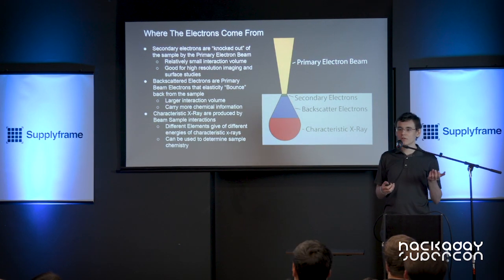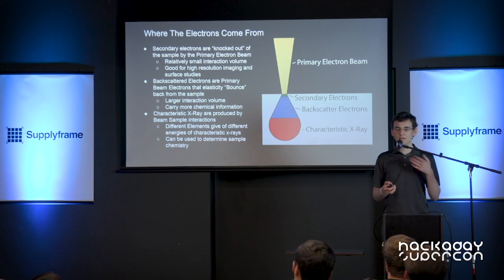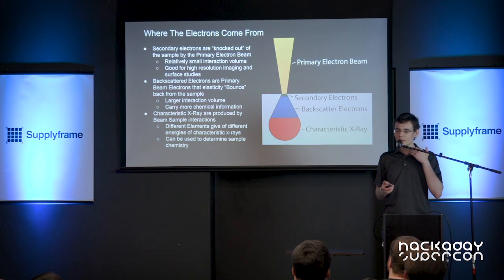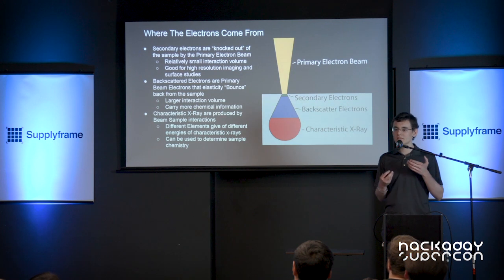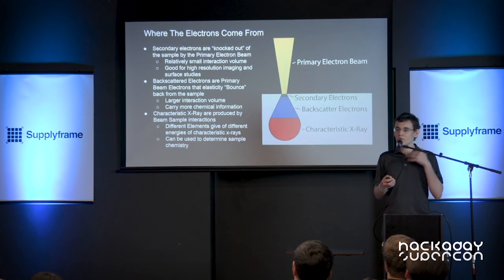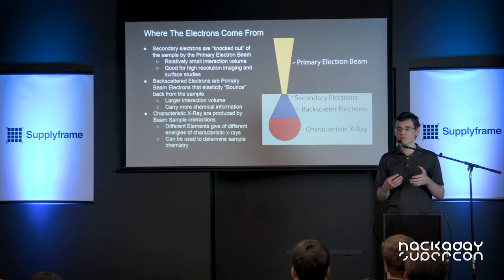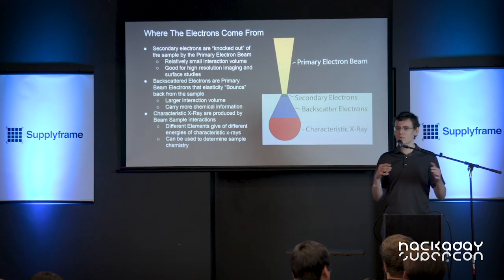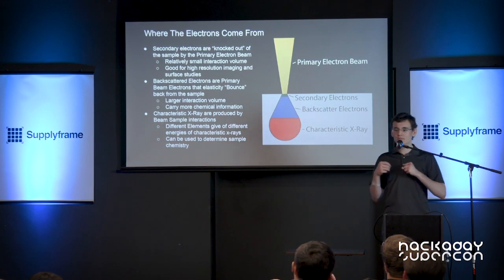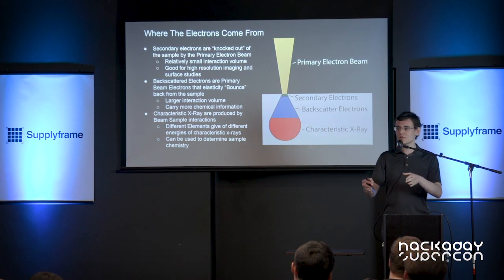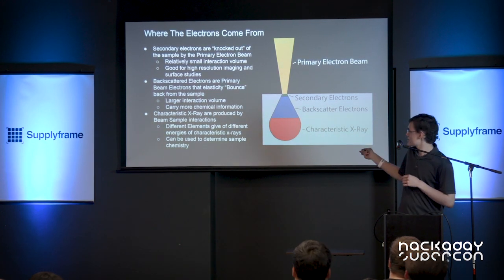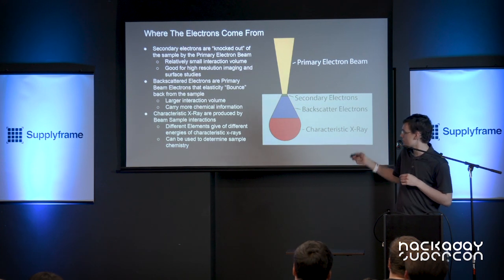The other type of electrons we're going to look at are backscatter electrons. Backscatter electrons are primary beam electrons that are elastically scattered back from within the sample. Because of that, they can carry more chemical information, because atoms with a higher atomic mass will reflect more backscatter electrons. So we can use this to determine some chemical properties of the sample, or if we just want to see a little bit deeper into the sample, we can use those backscatter electrons because they come from that much larger interaction volume.